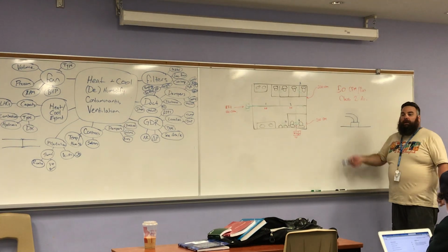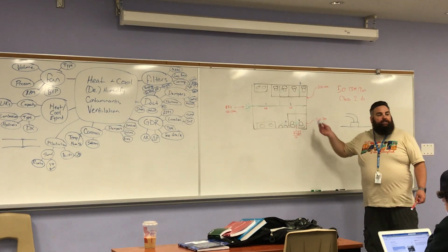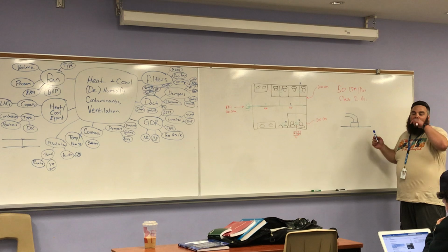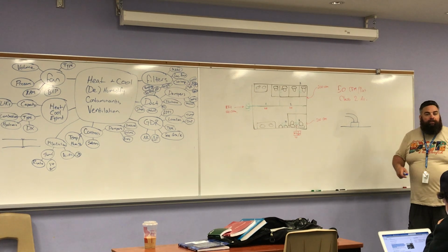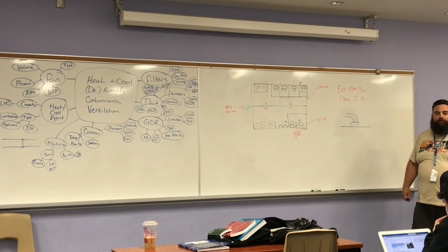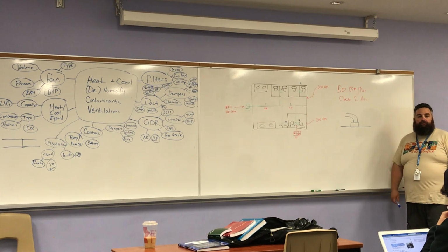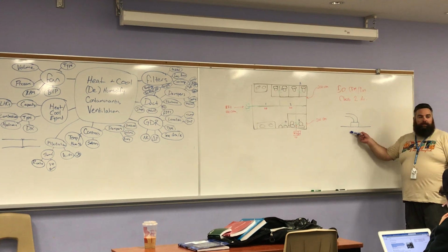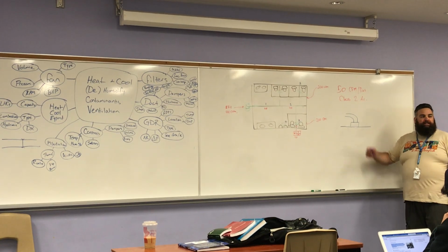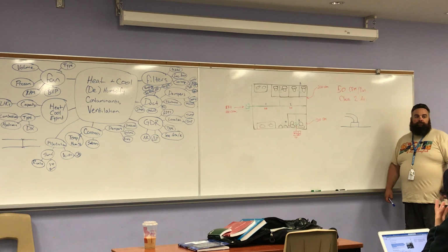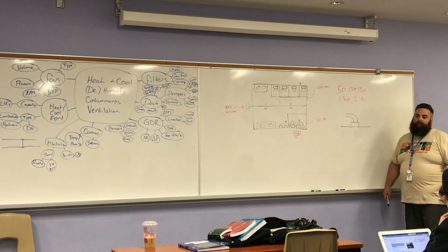You have to think about all this as the designer. What's this going to look like? You can't just leave it up to other people because we have to account for all the pressure drops. So if you're the air, what's the first thing you have to pass through? The free area. The free area of my egg crate. What's the next thing you have to do? The fitting? The 90?